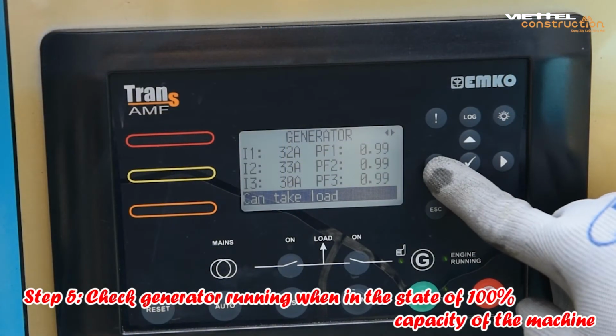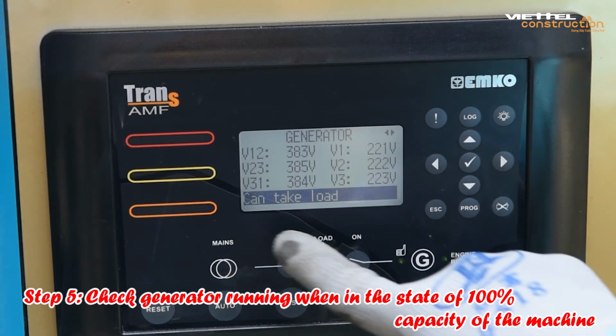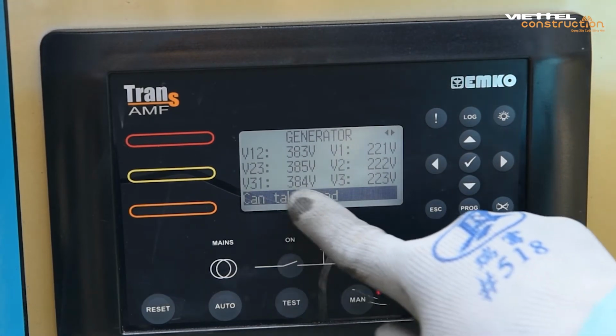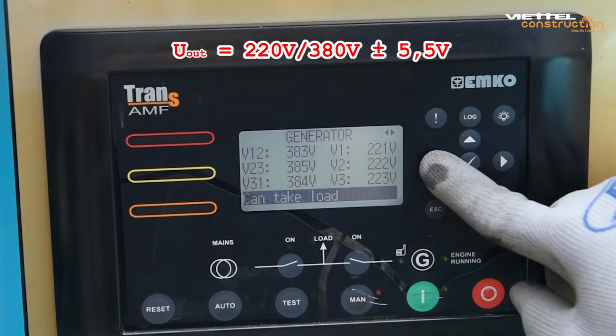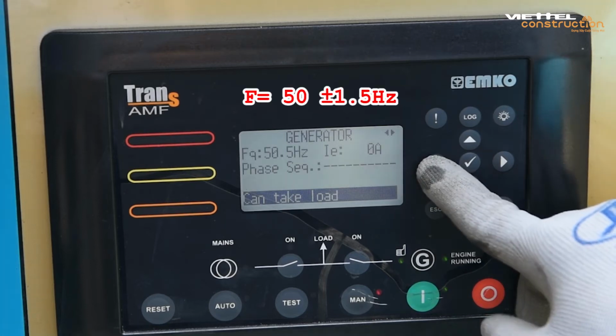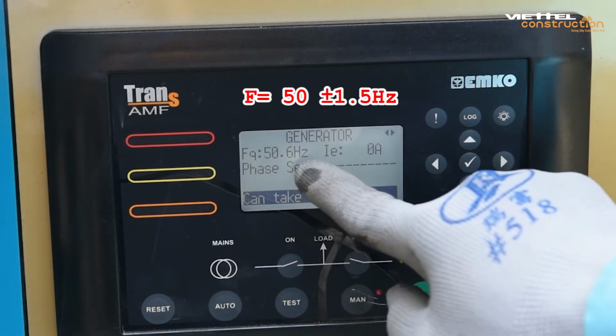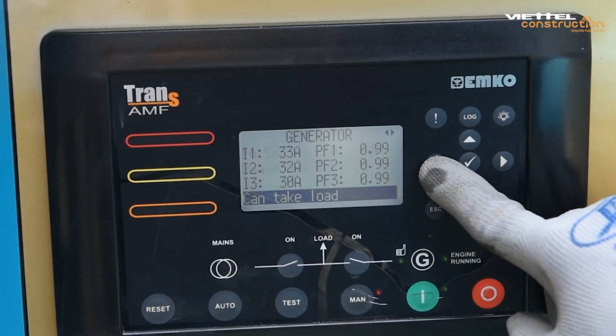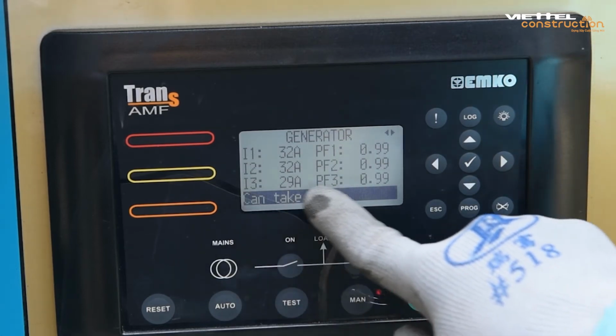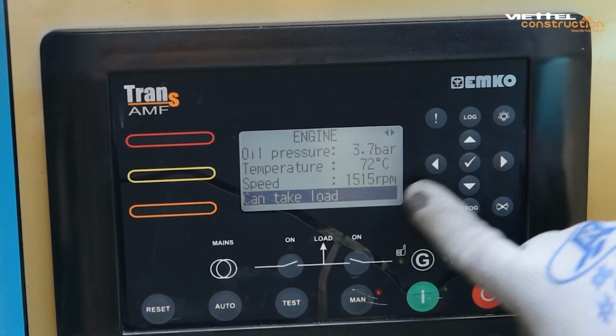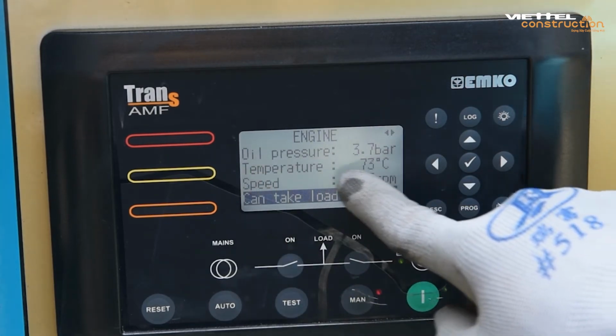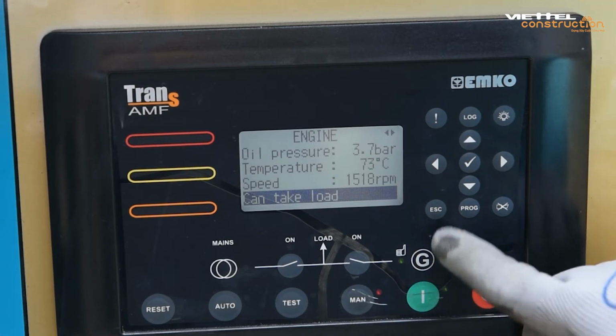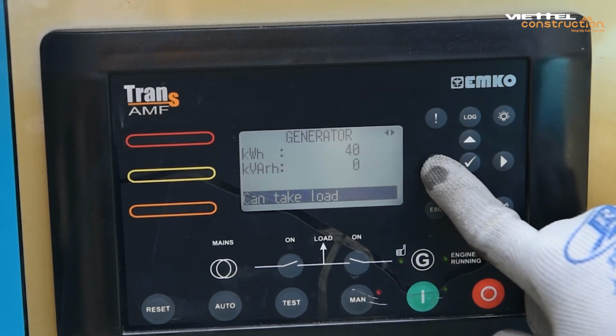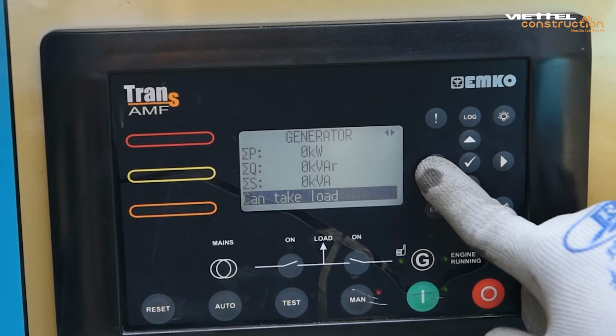Step 5. Check generator running when in the state of 100% capacity of the machine. After closing the load, the parameters must reach the following threshold: output voltage, U out equal to 220 volts over 380 volts plus or minus 5.5 volts, frequency, F equal to 50 plus or minus 1.5 Hz. The total consumption current of the station must not exceed the allowable current of the generator. If the above parameters are not reached, the machine must be stopped to recheck, to adjust and to fix.